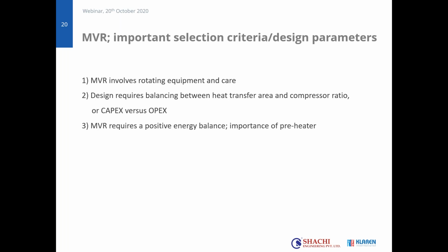In fact, the choice is between investing upfront, that's more heat transfer area, which would allow you to run at a lower compressor ratio. Or you can choose to say, I accept a bit higher OPEX, so I run at a bit higher compressor ratio, but then I need less heat transfer area. I have a more compact unit. But they go hand in hand. I will explain.